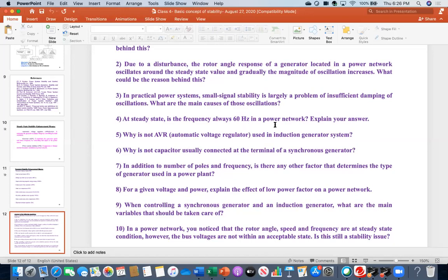Yeah, it has to be maintained. Okay, but you see, why I mention always is that sometimes it might be 60, but in real practice it is very difficult to maintain that exact number because always there is some sort of change, some load change happening continuously. There should be around plus or minus 10% deviation. Not plus minus 10%, plus minus 3%. Yeah. So everybody keep in mind, there is a frequency range.